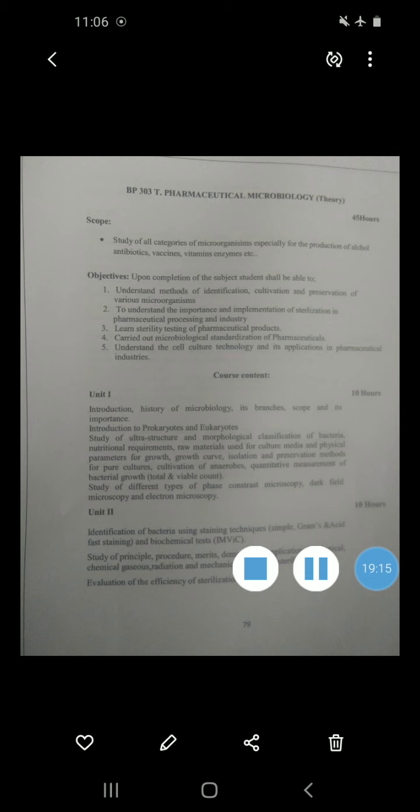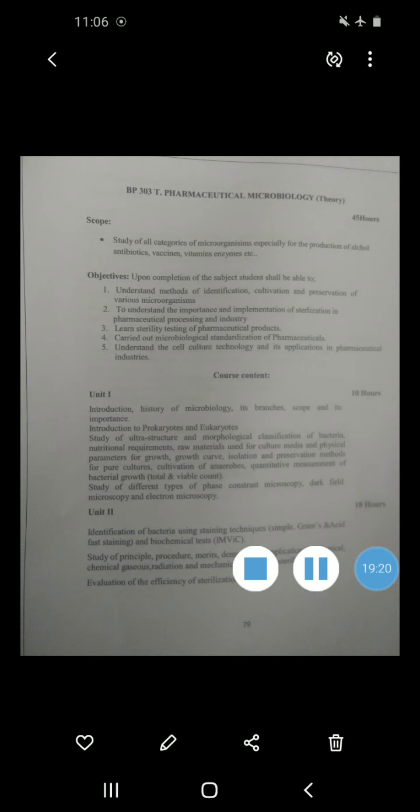The sterilization methods are evaluated to ensure the yielding of the best quality products. The process, controls and finished products do not sufficiently assure the product quality. When a specific part of the total product is tested and passes the sterility test, it does not indicate that the complete product is sterilized.